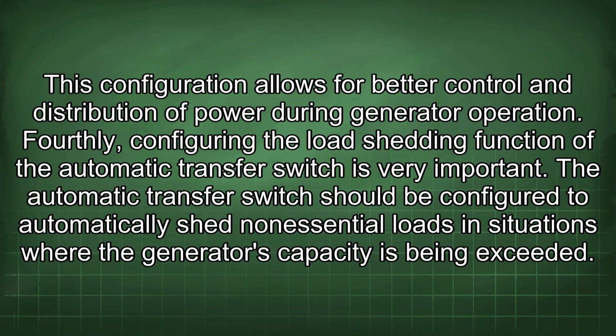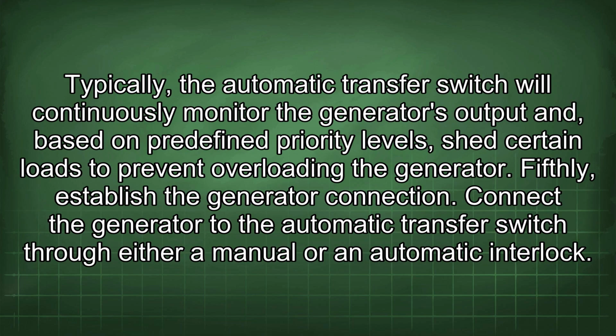Fourthly, configuring the load shedding function of the automatic transfer switch is very important. The automatic transfer switch should be configured to automatically shed non-essential loads in situations where the generator's capacity is being exceeded. Typically, the automatic transfer switch will continuously monitor the generator's output and, based on predefined priority levels, shed certain loads to prevent overloading the generator.